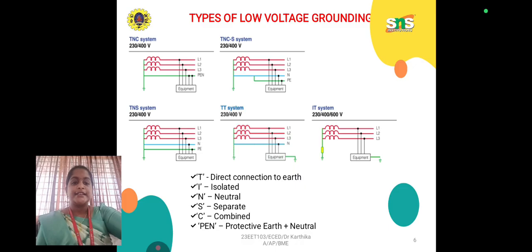See the low voltage grounding types. First one, the TNC system. Direct connection to earth is T, I is isolated, N is neutral, S is separate and C is combined. Here we have PEN, a new term, protective earth plus neutral. The first one is a perfect example of the TNC system, either single phase or three phase. Single phase means 230 volt and three phase means up to 400 volt. Then the TNCS system, and the third one is the TNS system, TT system and IT system. Based on the consumer needs and applications, we prefer either TNC, TNCS, TNS, TT or IT system.